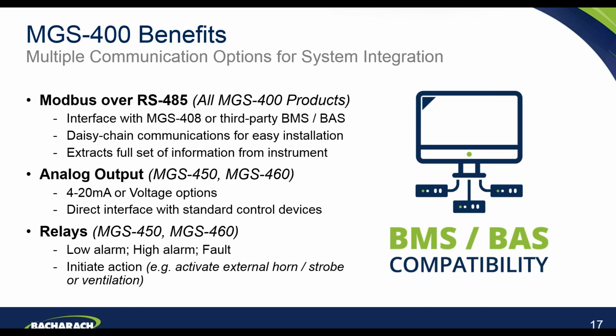On the MGS-450 and 460, they both come with an analog output. This can be configured by yourselves and the customers to be 4 to 20 milliamp or voltage. And again, what this enables is simple direct interface with standard control devices in the marketplace. In addition to the analog output, the 450 and the 460 versions also come with relay outputs. There are 3 relay outputs built into each of those, and that allows for low alarm set point, high alarm, and also fault alarm. And again, this assists our customers to ensure that they can initiate action on alarms such as activation of mechanical ventilation, activation of external horns and strobes, for example.